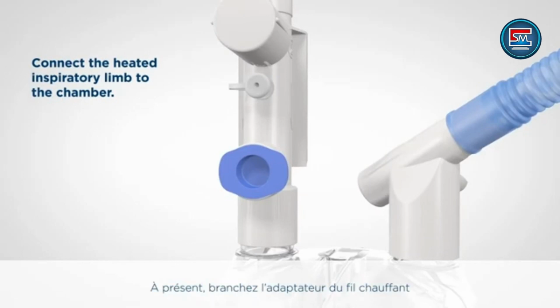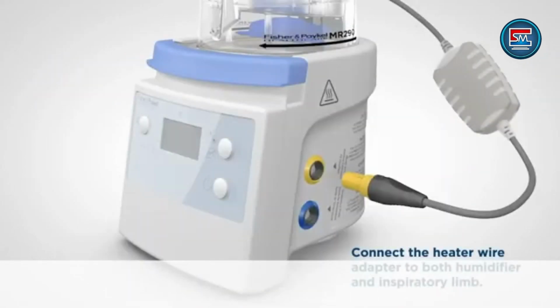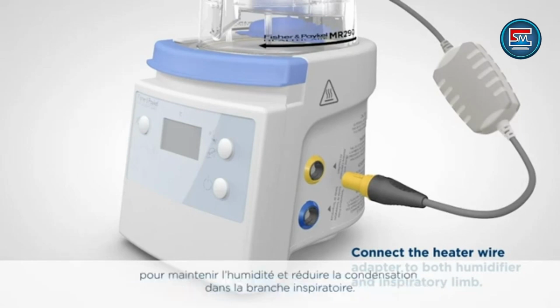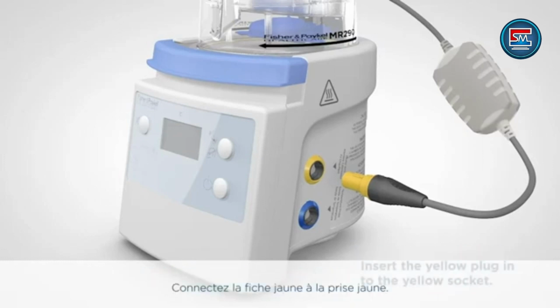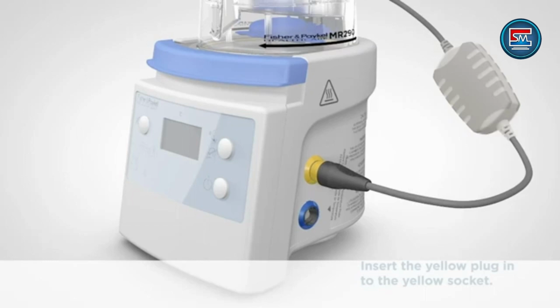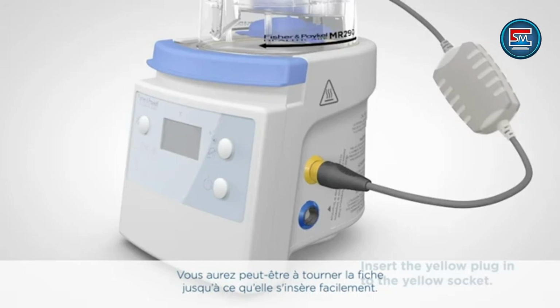Now let's connect the heater wire adapter and temperature and flow probe adapter. First, let's connect the heater wire adapter. This adapter connects the heated inspiratory limb to the humidifier and provides energy to power the wire in the limb. The humidifier adjusts the energy delivered to the wire to maintain humidity and reduce condensate in the inspiratory limb. Connect the yellow plug to the yellow socket. The socket is both color-coded and keyed to the plug. You may have to turn the plug until it slides in easily. It should click into place.